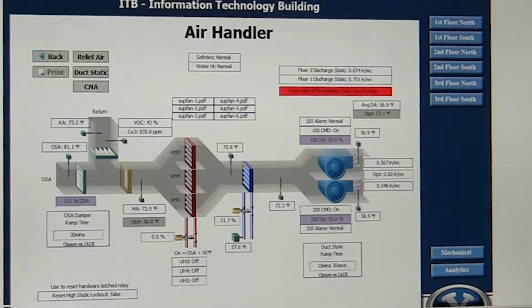Another way we've done it in this situation is we've put data loggers in the air handler and logged it with the computer over the course of a few days. Then we can trend them together and see the temperature difference, do a calibration, and then log it again for 3 days to see if they've actually come in line.